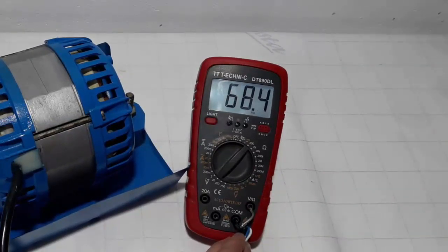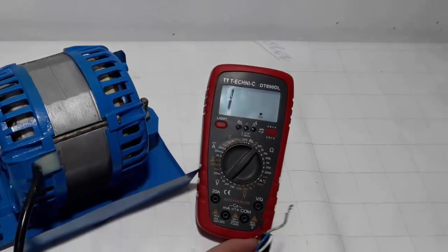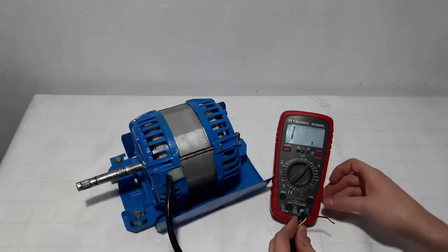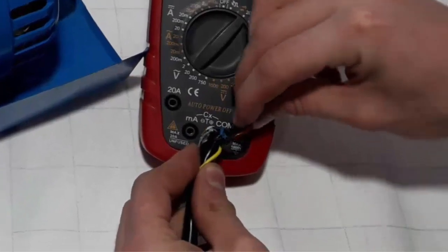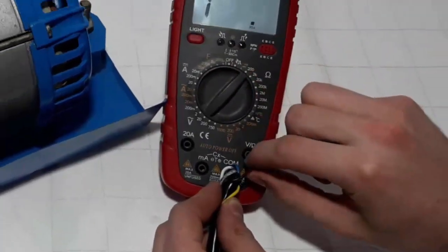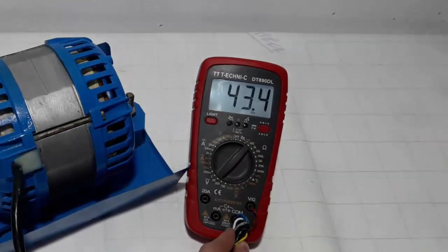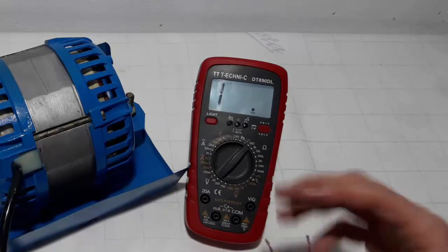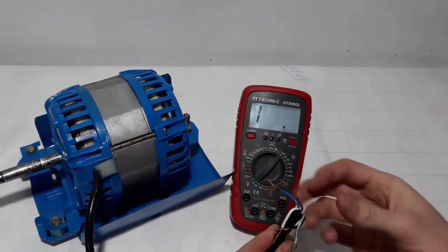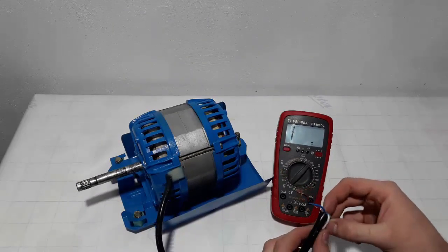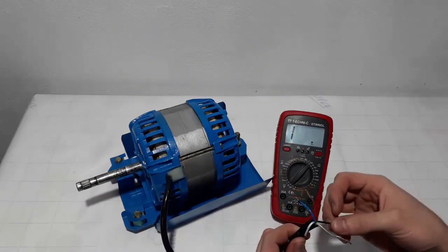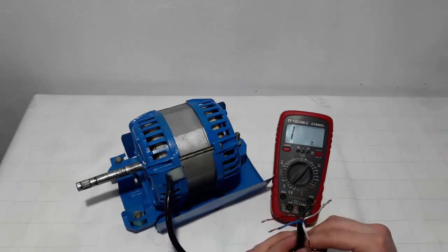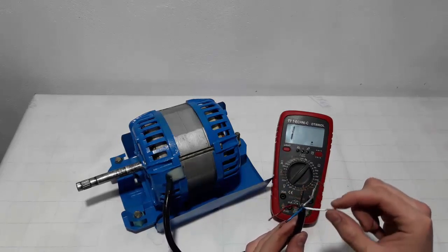When we measure resistance between black and gray wire, we get 68 ohms. Now we measure resistance between blue and red wire and we get 43 ohms, which is smaller than the first resistance. So black and gray wires are for the low speed coil, red and blue are for the high speed coil, and the last wire, the white, is the common.